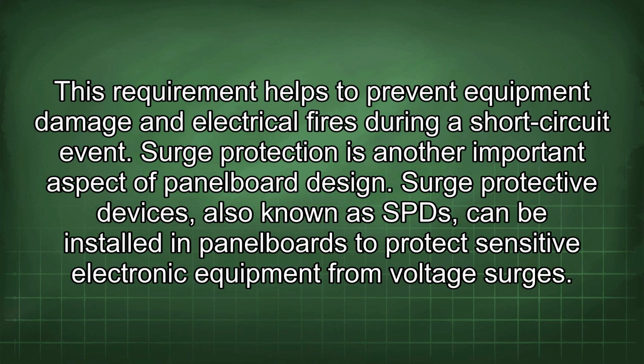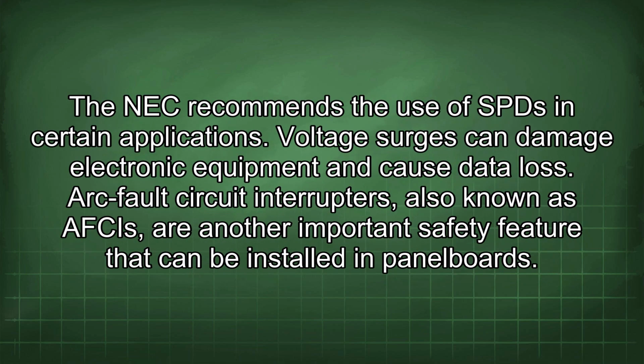Surge protection is another important aspect of panel board design. Surge protective devices, also known as SPD, can be installed in panel boards to protect sensitive electronic equipment from voltage surges. The NEC recommends the use of SPD in certain applications. Voltage surges can damage electronic equipment and cause data loss.